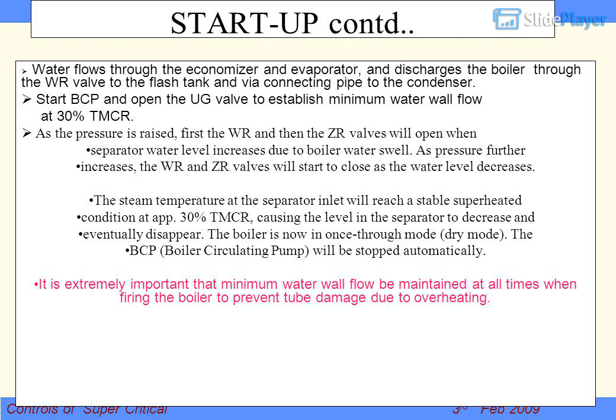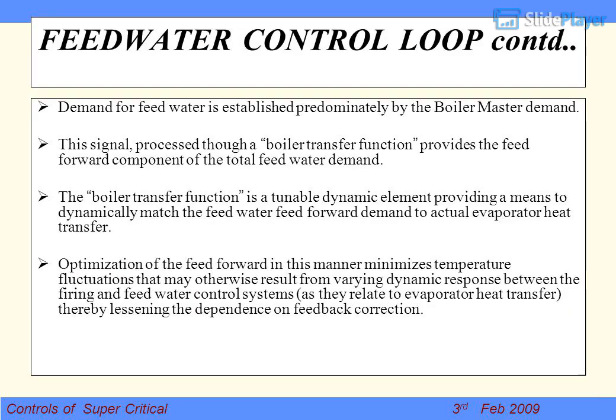It is extremely important that minimum water wall flow be maintained at all times when firing the boiler, to prevent tube damage due to overheating. Demand for feed water is established predominantly by the boiler master demand. This signal, processed through a boiler transfer function, provides the feed forward component of the total feed water demand. The boiler transfer function is a tunable dynamic element providing a means to dynamically match the feed water feed forward demand to actual evaporator heat transfer. Optimization of the feed forward minimizes temperature fluctuations that may otherwise result from varying dynamic response between the firing and feed water control systems as they relate to evaporator heat transfer, thereby lessening the dependence on feedback correction.